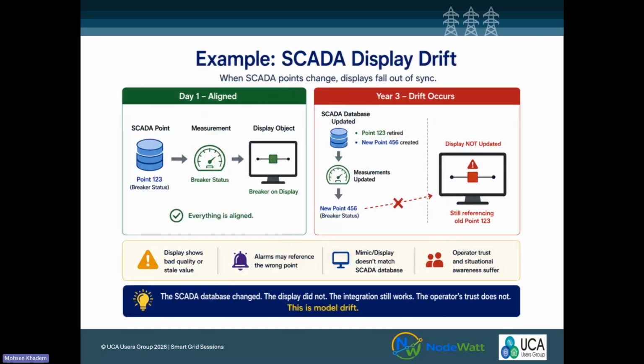SCADA display is a good drift example to talk about. At day one, you had all SCADA points mapped to your measurements. Measurements are linked to your displays. If something happened, you see it on your display, alarming, nicely showing which point has the value over the limit and so on. But later in your SCADA, the point is changed, correct? The new point is 4, 5, 6, and not 1, 2, 3 anymore.